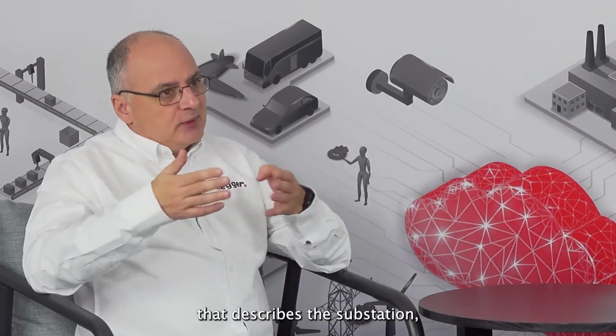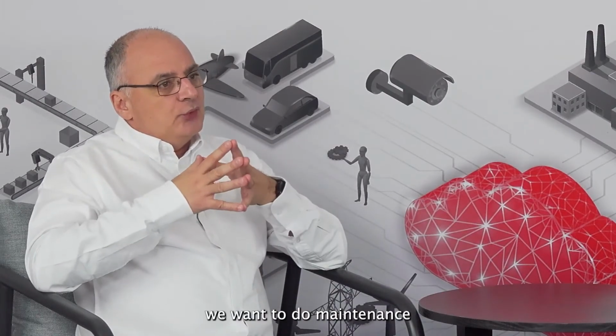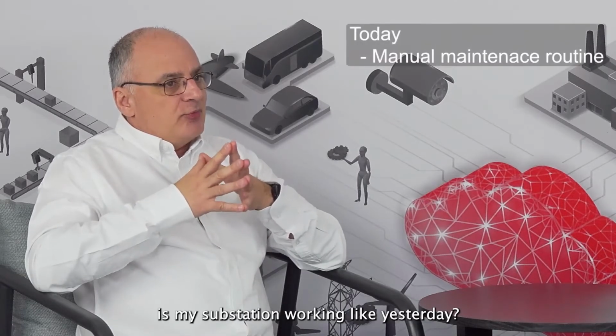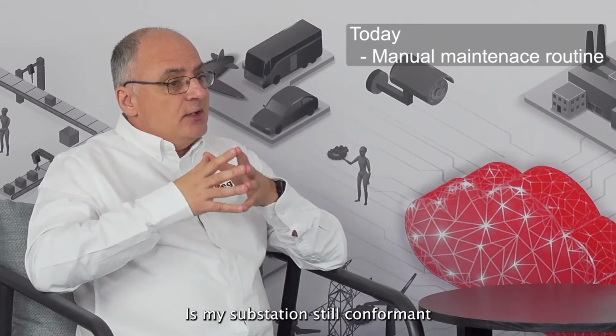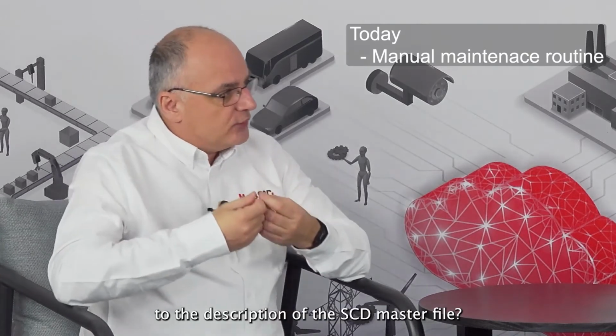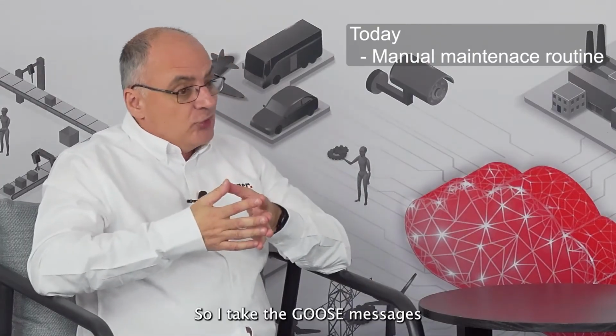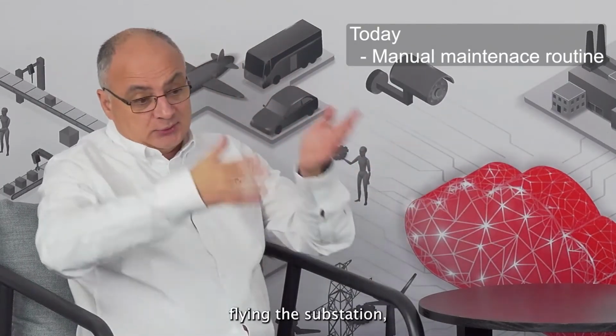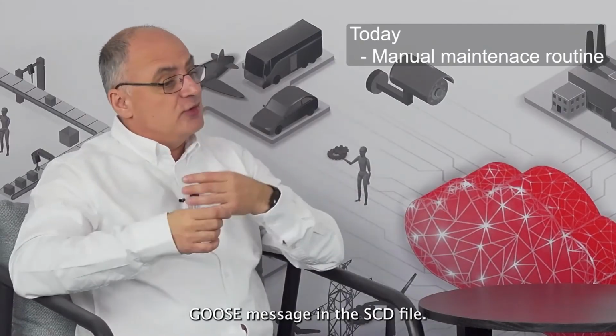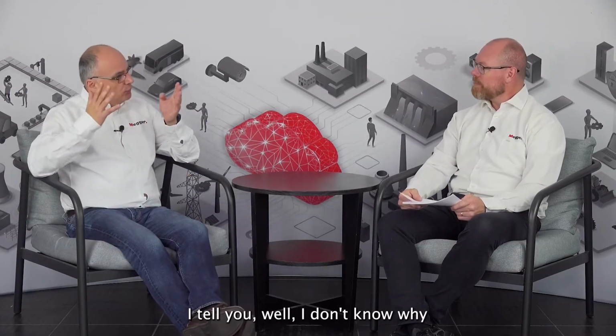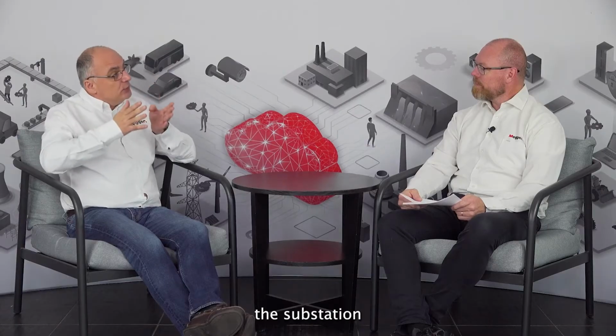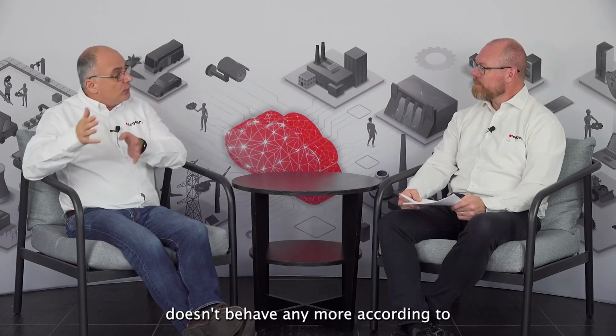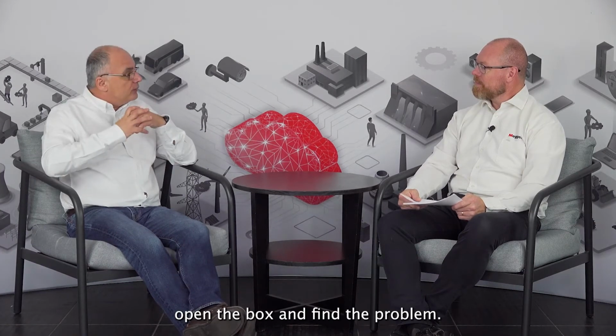Still, we have the SCD file that describes the substation. Still, we want to do maintenance routines and see: is my substation working like yesterday? Is my substation still conformant to the description of the SCD master file? So I take the GOOSE messages flying in the substation and compare them with the GOOSE messages in the SCD file. Every day I can do this. And if I find a difference, I tell you, I don't know why, but there is a problem. The substation doesn't behave anymore according to what is written in the SCD file. Automatic maintenance routine flag: let's go and open the box and find the problem.